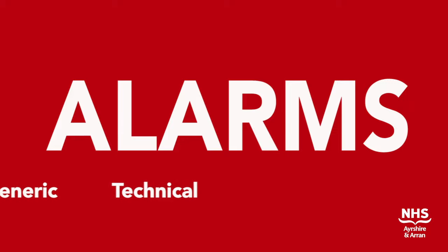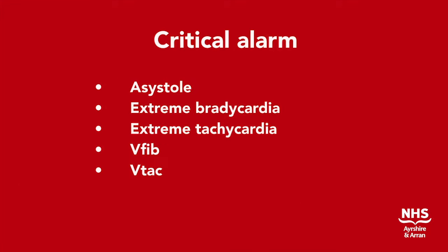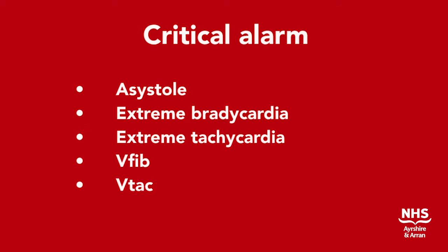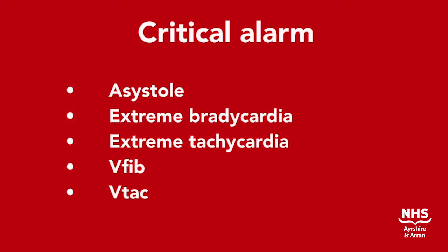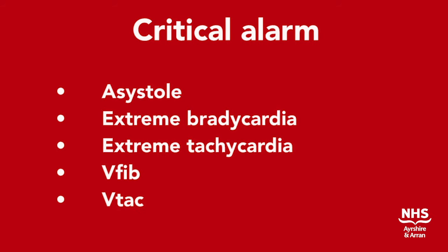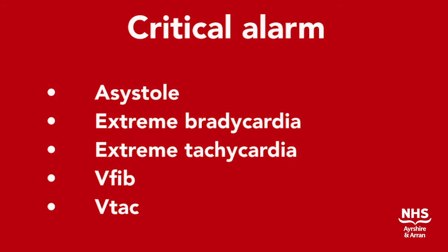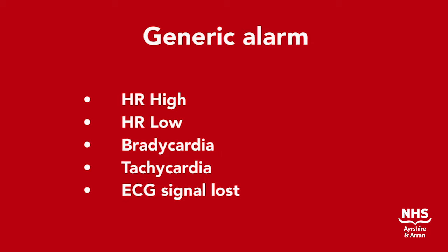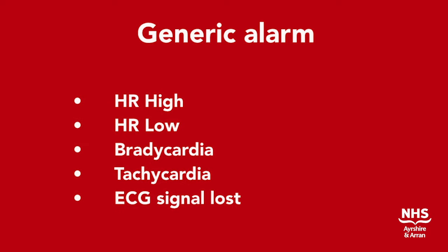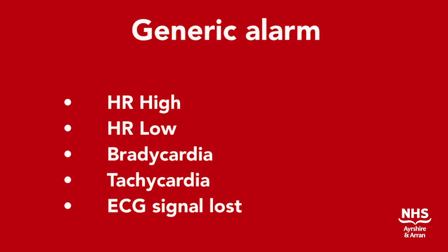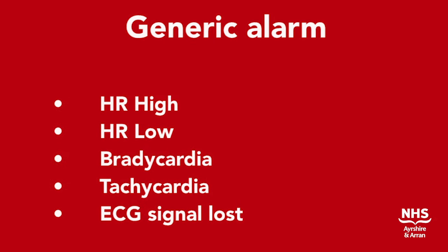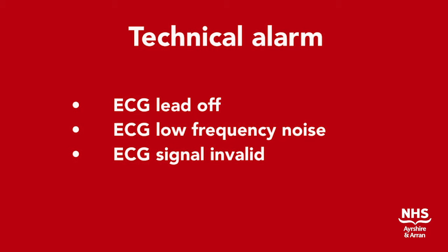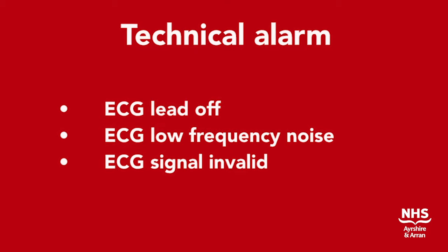Whilst the patient is on telemetry, there are several different alarms that may be encountered. Critical alarms include asystole, extreme bradycardia, extreme tachycardia, V-fib (ventricular fibrillation) or V-tach (ventricular tachycardia). Generic alarms include heart rate high, heart rate low, bradycardia, tachycardia and ECG signal lost. Some of the technical alarms include ECG lead off, ECG low frequency noise and ECG signal invalid.